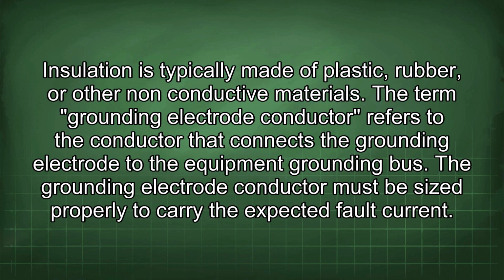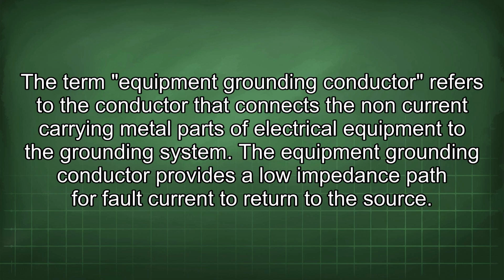The term grounding electrode conductor refers to the conductor that connects the grounding electrode to the equipment grounding bus. The grounding electrode conductor must be sized properly to carry the expected fault current. The term equipment grounding conductor refers to the conductor that connects the non-current carrying metal parts of electrical equipment to the grounding system. The equipment grounding conductor provides a low impedance path for fault current to return to the source.